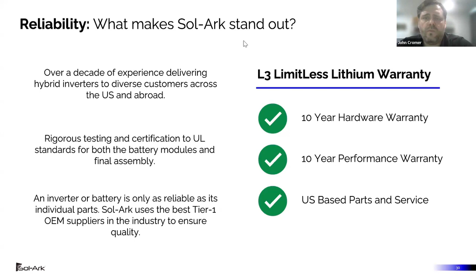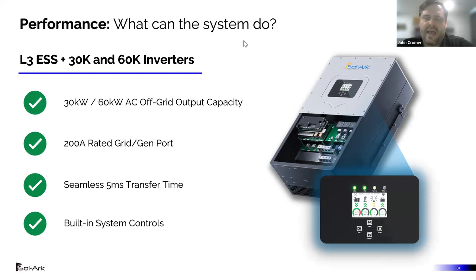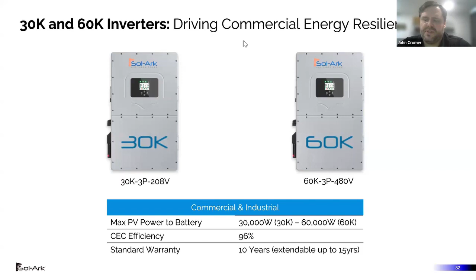Our hybrid inverters are capable of seamless transfer time. That is because we do not have separate energy management panels from the inverter. So when we do a hybrid inverter, it is not just about combining the batteries and the solar array. It's also combining that grid interconnection and management point. Again, our 30 kilowatt and our 60 kilowatt inverters have been on the market for over a year now. 10-year out of the box warranties. Basically, you select the 30K for 208 3-phase, the 60K for 480.